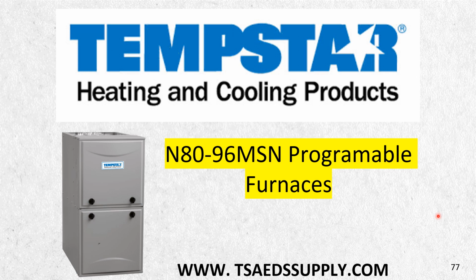Because you got to keep in mind, you as the contractor sold the homeowner on what a good product you sell and what a good product you install. It's a good idea to make sure you read the install manual on how to install that product that you were bragging about to even get the job, and then make sure that product has enough CFM and airflow going through it. And then make sure you have everything set up with your static pressure so that you have a long life. And then make sure you have your sediment traps, your drains working right, so that heat exchanger does not draw moisture in, and you give a short life to that furnace.